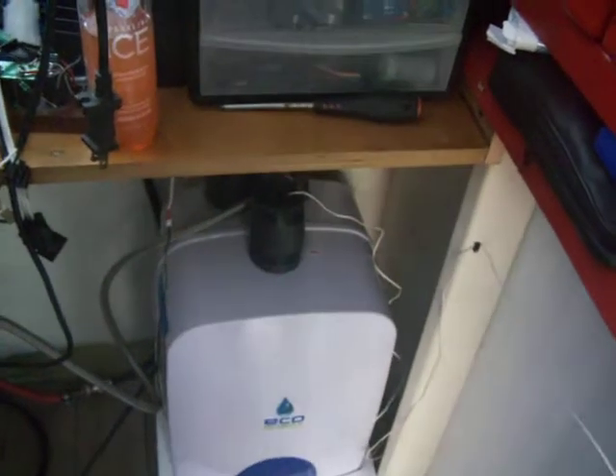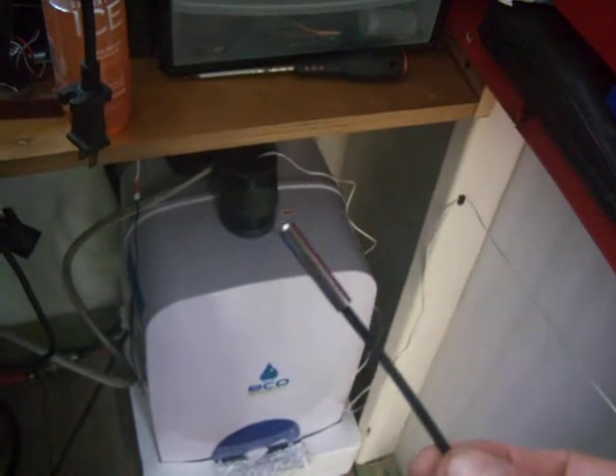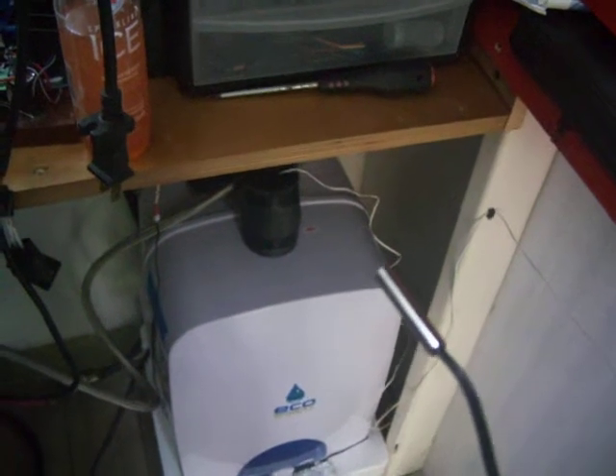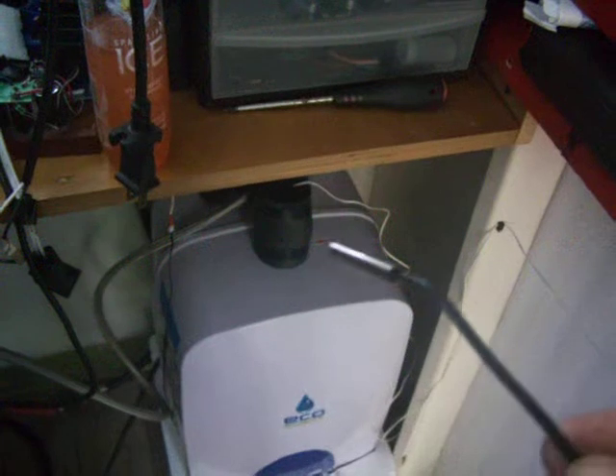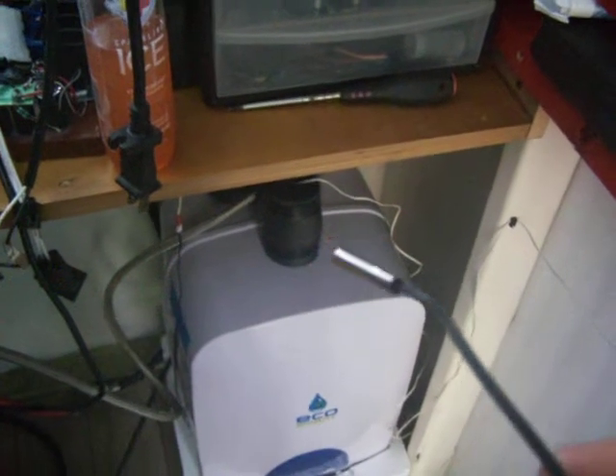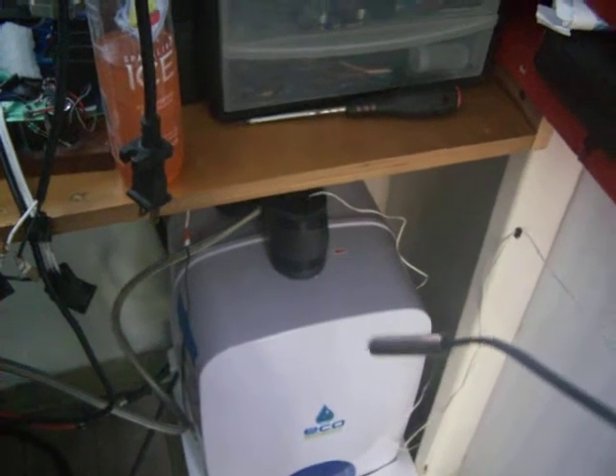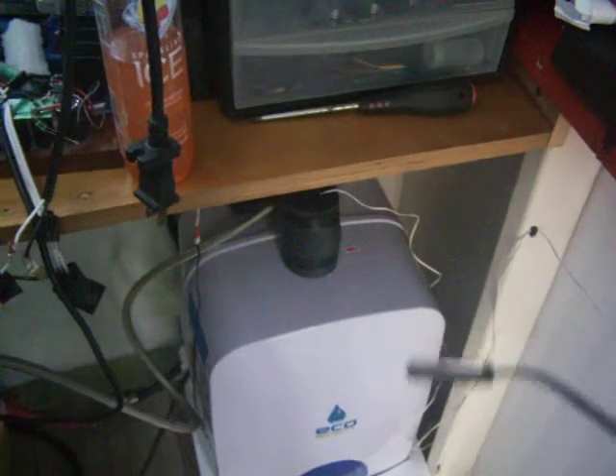It is 123.3 right now — that's just being measured underneath that black foam, that's the over-temp pressure relief valve. Before putting this thing in, I attached one of these resistive temperature sensors. There's a deep well where they put the temperature sensing tubes, and you can stick this in there about eight inches or so. I wedge it in with some foam, then cut a little notch with a file on the bottom cover.